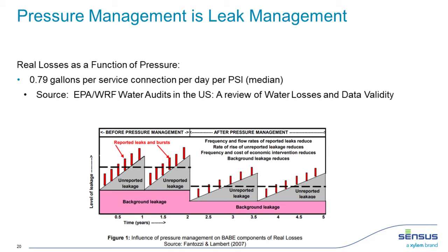So we're looking at reducing our pressures through the winter. We have to keep our pressures up for irrigation in the summer. The next step we're looking at is controlling PRVs so we can reduce pressure during the day and increase it at night for the irrigation systems. Hopefully for 12 hours out of every day, we can reduce that leakage rate a bit.